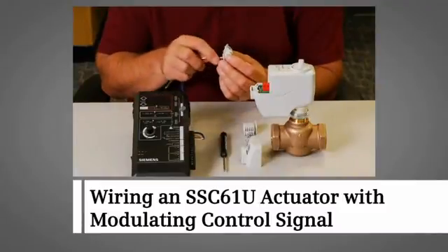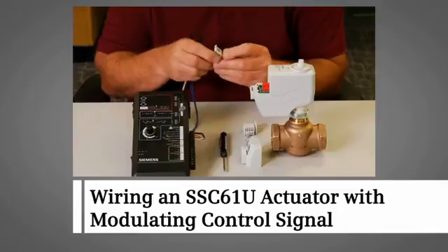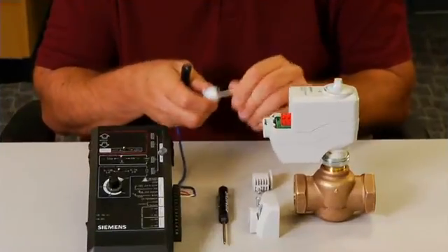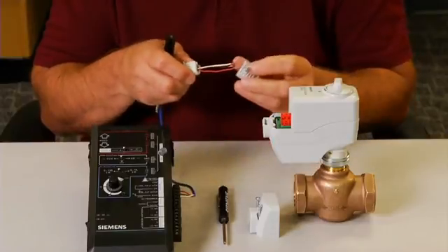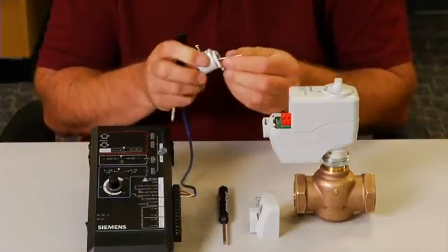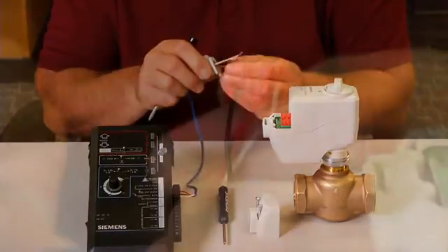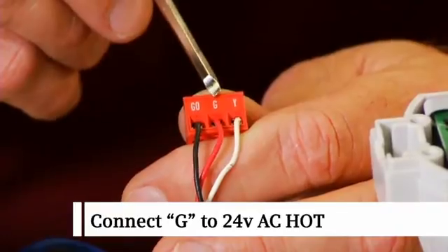This video demonstrates wiring of the SSC 61U to a controller that uses a 0 to 10 VDC control signal. First, we need to terminate three wires to the actuator's terminal block. Feed the wiring through the cabling adapter and then connect G to the 24 volt AC hot terminal.